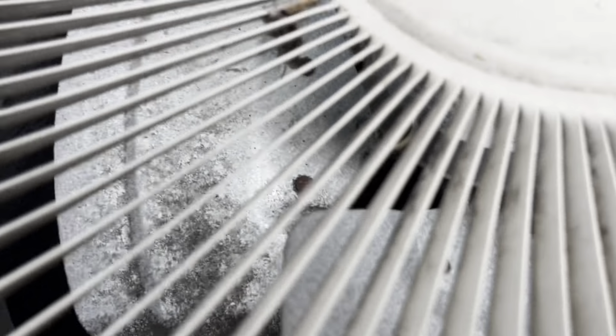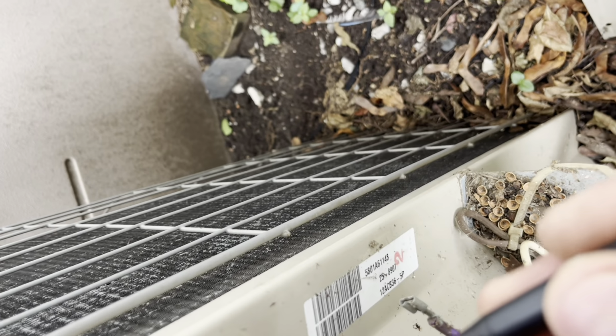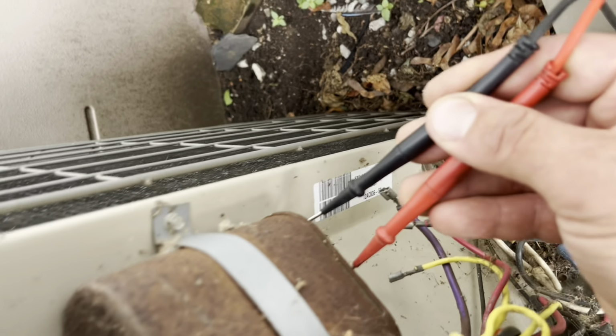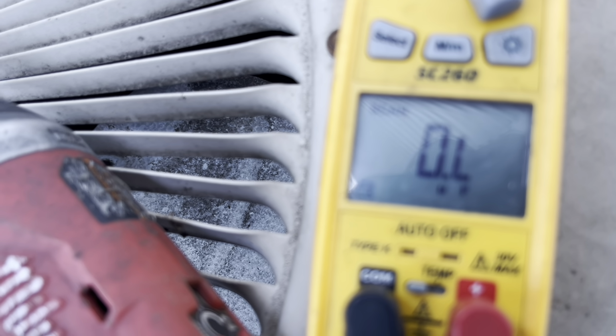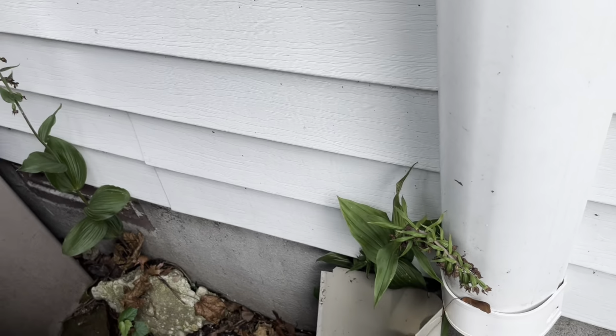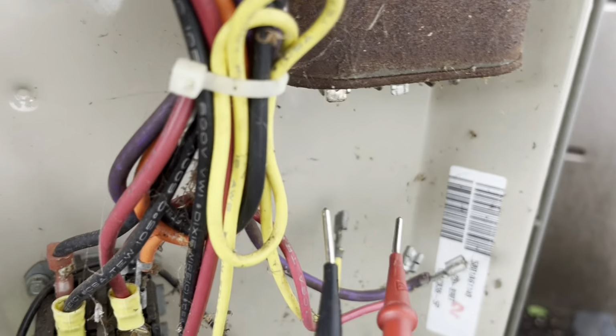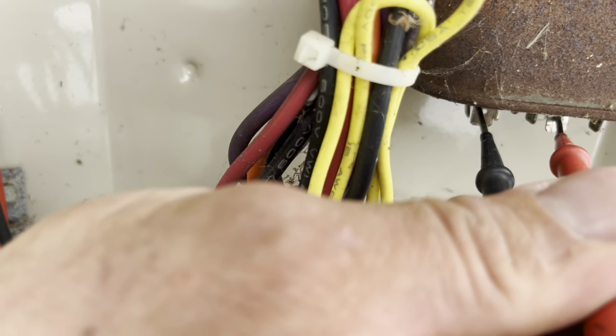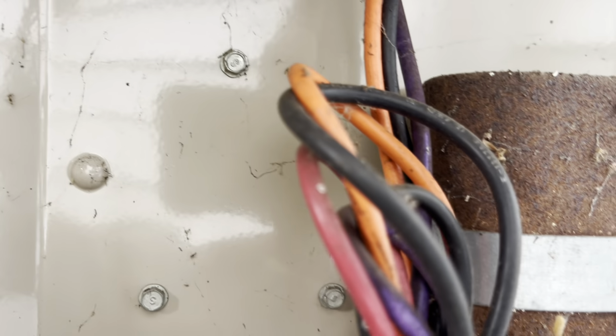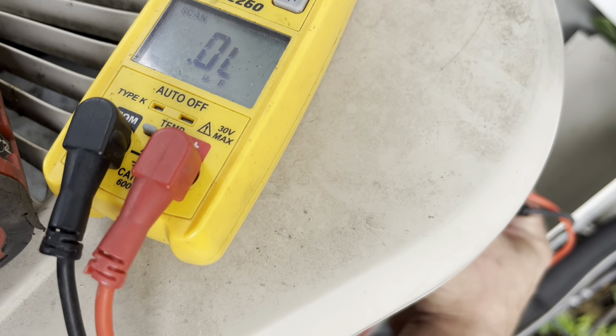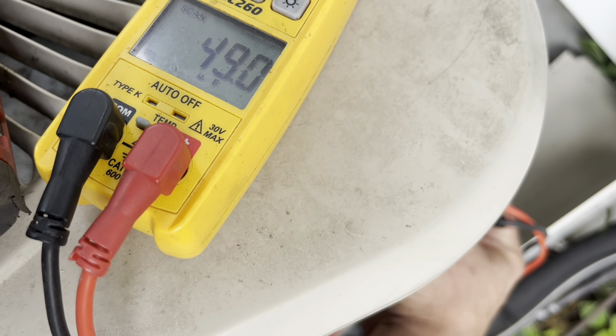So we got a 5 microfarad capacitor. We're gonna go common to fan. Then we're looking for common to Herm, which is your compressor terminal. It's supposed to be 50. Don't ask how I know that, but I do. 49.